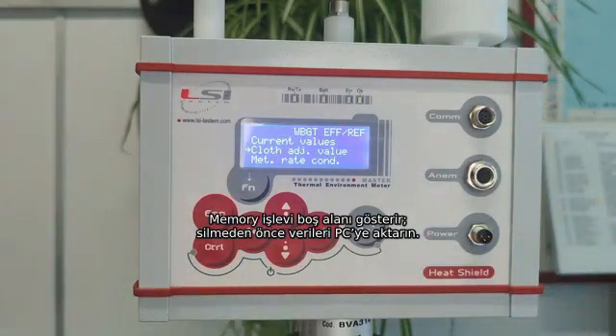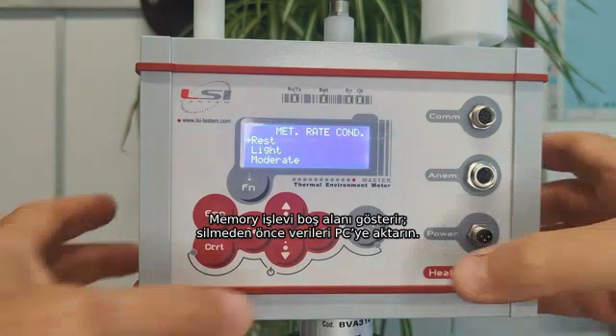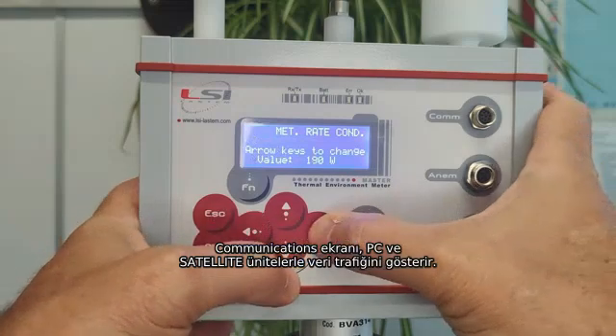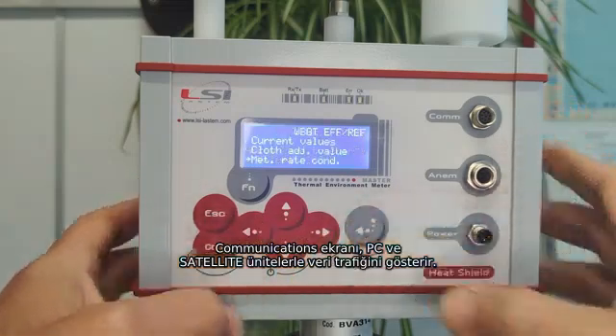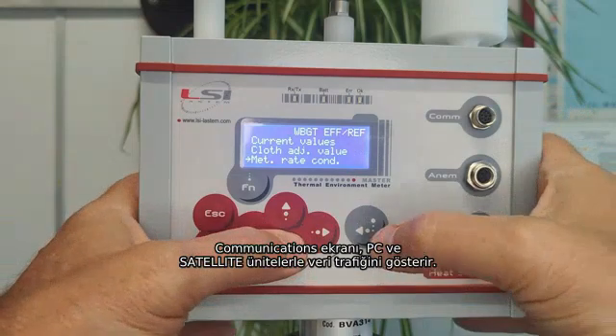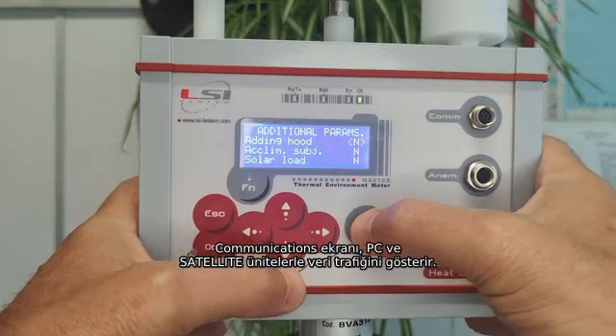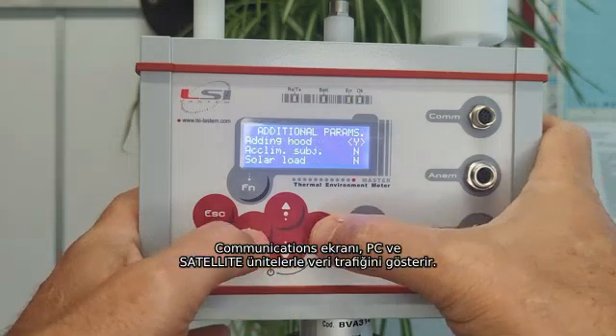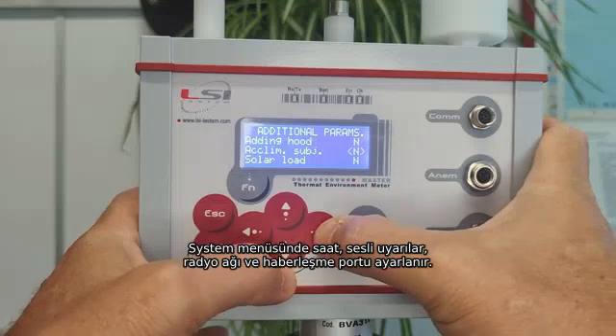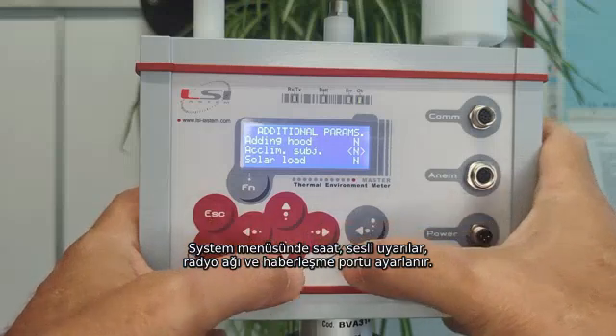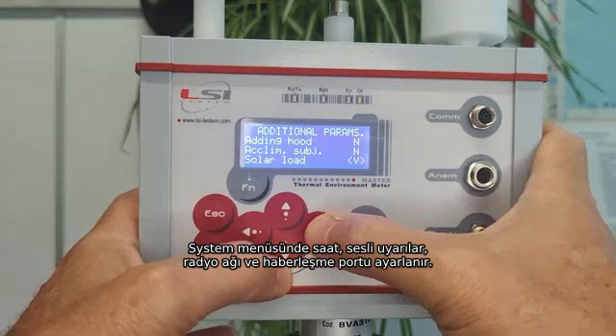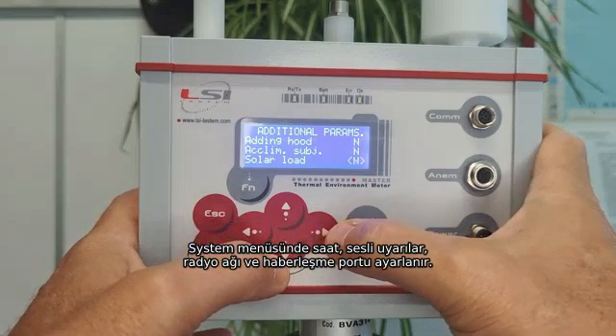Next, to obtain the correct WBGT reference value and the corresponding delta to the WBGT effective value, metabolism rate conditions need to be set. Even in this case, it is possible to edit the proposed value. Additional parameters are required. As the presence of the hood, it can be added to the selected clothing factor.